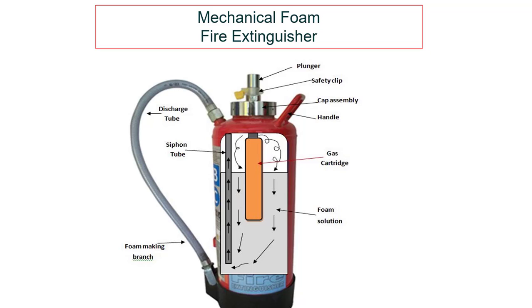Mechanical foam fire extinguisher — you can see the difference between the water type and mechanical foam type: there is a pressurized gas cartridge inside, and instead of water, foam solution is filled. The parts include a plunger inside the handle, safety clip, gas cap assembly, handle, discharge tube, and siphon pipe. When you press the plunger, it punctures the gas cartridge — which is at high pressure, maybe 25 to 30 kg per centimeter squared — and this creates a reaction with the foam solution, forcing the foam through the siphon to extinguish the fire.